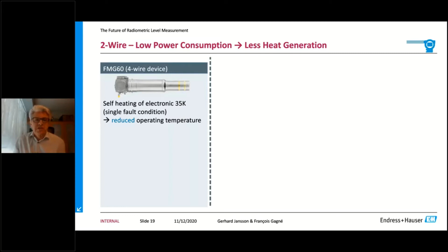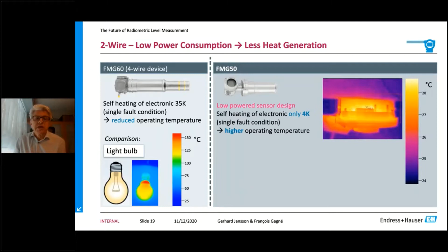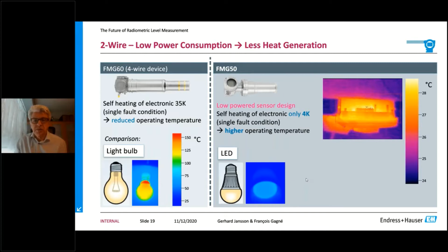So to achieve loop powered, we need to do something. We need to reduce the energy consumption of this device. A 4-wire device, if we compare this to a light bulb, would be like the old style light bulbs. The new FMG50 would in comparison be like those new LED light bulbs, a lot less energy hungry, and by that we can also make this a loop powered instrument. There are also other benefits that I'll come to that we can achieve by having a loop powered instrument with a lot less energy consumption.